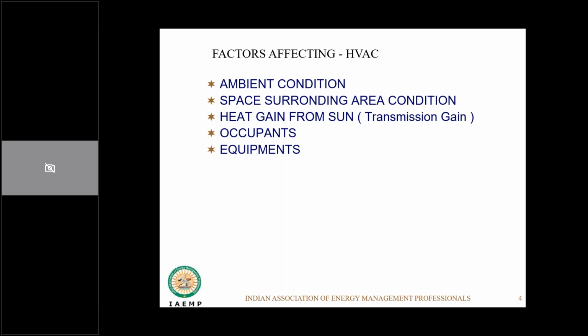The main factor while you're dealing with equipment is to understand what the diversity factors are. Normally what happens is we sometimes take the nameplate value or the rated kilowatt value of the equipment in design, but in practical experience we feel that the actual power drawn, the actual energy consumed by this equipment, may be much lower than what is rated, and those rated powers usually come very rarely for a very short period of time. Otherwise, it works normally between 60 to 80% of its rated capacity. Depending upon your use, you need to use a proper operating factor or a diversity factor to arrive at the right value for heat load design.